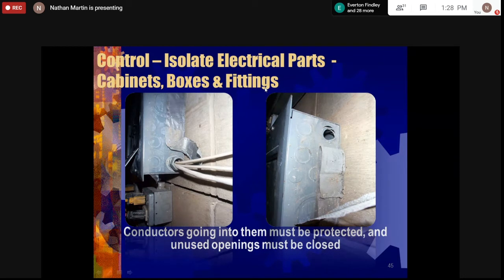Question: what if you used a flex conduit instead? Referring to the diagram on the left, yes, you can use a flex conduit, but you have to size it properly to allow the space factor for the three cables in there. If I'm using a flex conduit, though, I would not want to use sheathed cable - I would just use single core cable.